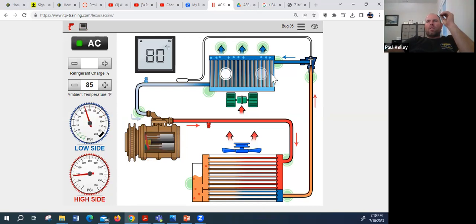Down here, we're at 75 and 80. Yeah, so our evaporator is definitely warm. Coming in, we got 107 and we go to 70, so it doesn't seem like a crazy restriction. Coming out, 70, 98, 100, 95, so this doesn't seem overly hot.